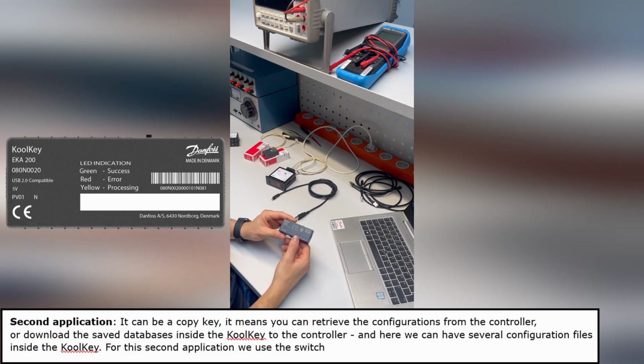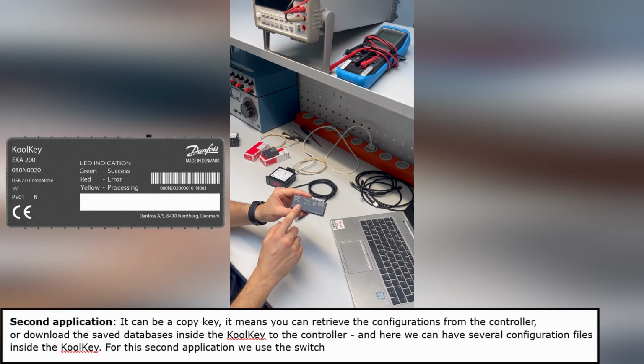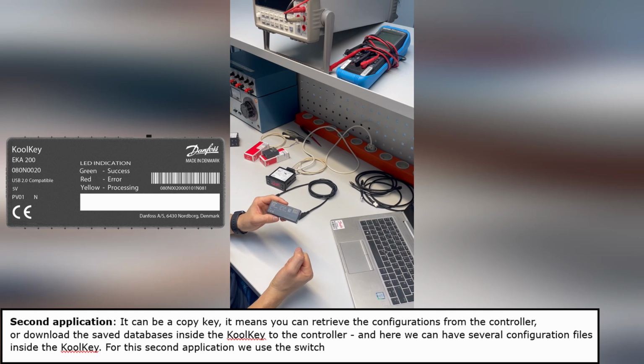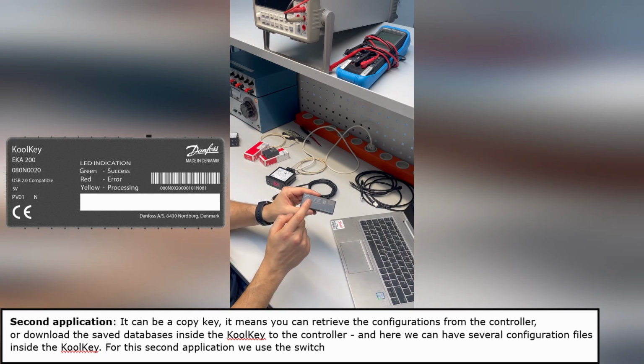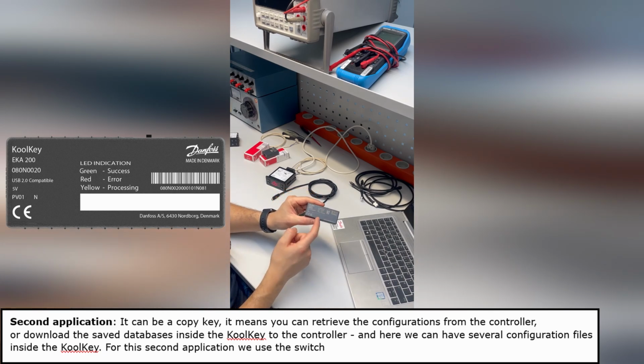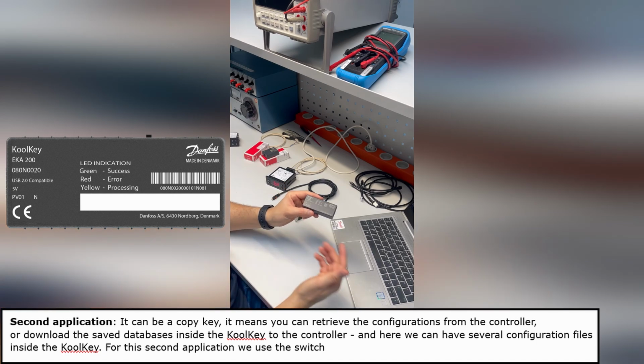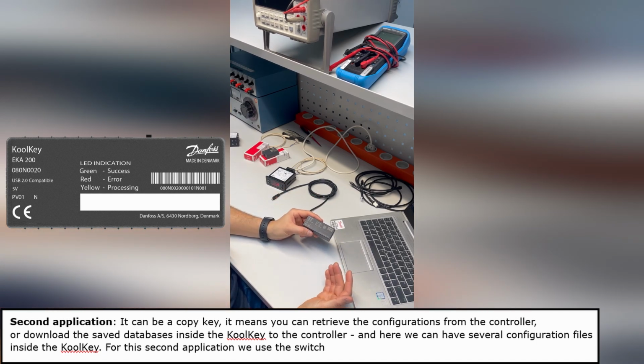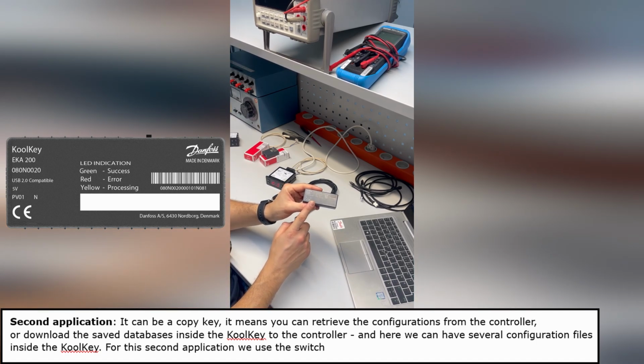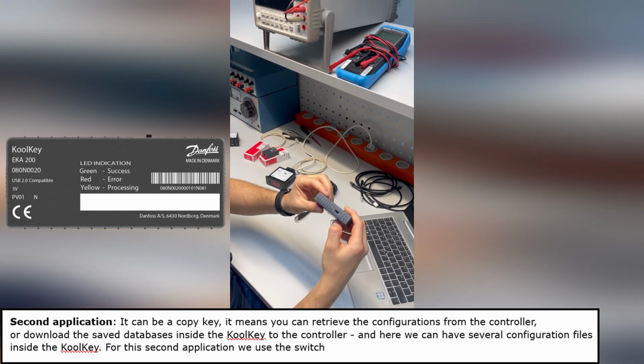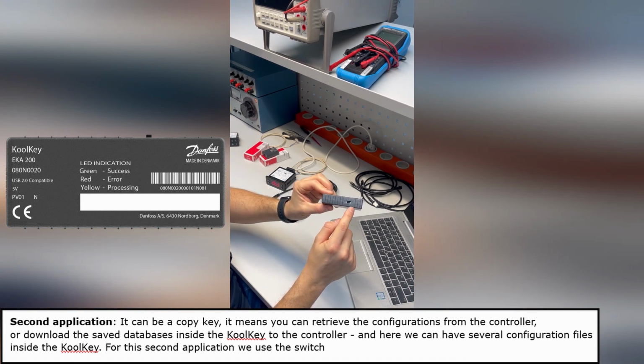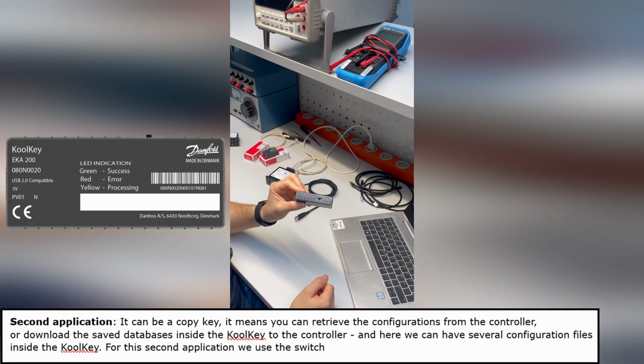The second application of the KoolKey is that it can also be a copy key. This means that you can retrieve the configurations from the controller or download the saved databases inside the KoolKey to the controller. And here we can have several configuration files inside the KoolKey. For this second application, we use the switch. So here you can define if you will read or if you write in the controller.